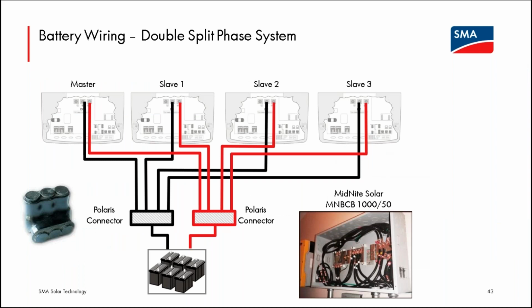Each cluster of Sunny Islands, even up to 4, must connect to 1 battery bank. So looking back at the lead acid system, if you have 3 strings of batteries wiring to 4 Sunny Islands, those need to be paralleled at some point. Big Polaris lugs is not going to cut it for a large system. Generally, the battery strings should come together on a large bus bar and then branch out to the 4 Sunny Islands. The insert picture shows a combiner box from MidNite Solar with 1,000 amp rated copper bus bars there in the center to do exactly that.